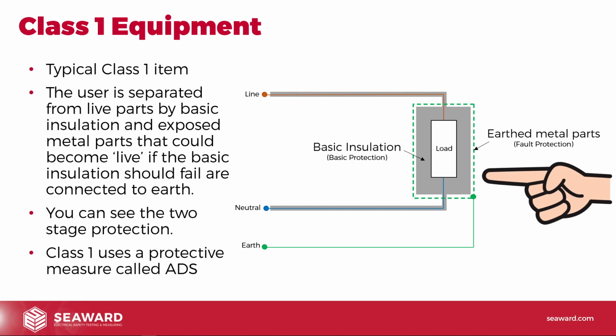Now, there is a bit of a curveball. You can get unearthed metalwork on equipment. Sometimes you might get the odd handle or the odd plate or bits of metalwork where you think it should be earthed and actually it isn't. And the reason it isn't is because the designer has decided that there's no way for it to become live under fault conditions. So potentially there's insulation between it and the live parts, or there's earthed metalwork there already.